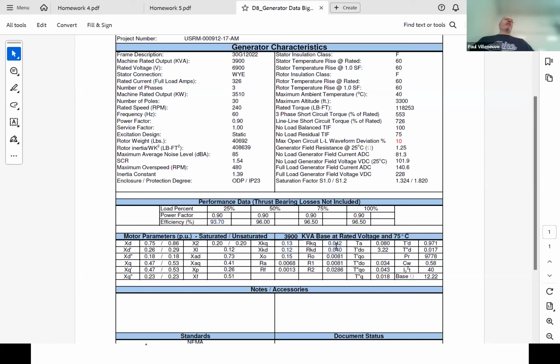The service factor is more of an application for motors. If a motor is 100 horsepower but has a service factor of 1.2, you could actually run it at 120 horsepower and the motor should still operate perfectly fine. Okay. Any other questions on this nameplate? This is a pretty basic data sheet, and it's only a 4 megawatt generator. I say only, but in the power world, that's pretty small. Okay, no other questions? All right.